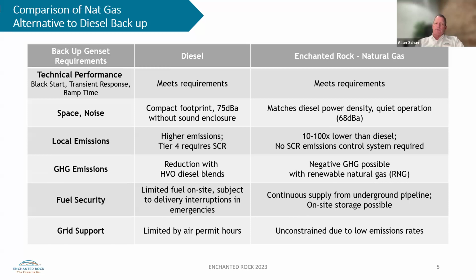Finally, a super important point: to support the grid beyond just power outages, a microgrid can provide an additional value stream that generates an economic revenue stream. Diesel generators have a very difficult time, if not impossible, running additional hours. In Northern Virginia, there was a request last summer to run additional diesel generation to support the grid, and it was met with a lot of resistance because of air emissions issues. A natural gas generator with clean emissions can run very easily, well within emission limits, and provide selective hours when the grid needs support by taking load off during those periods.